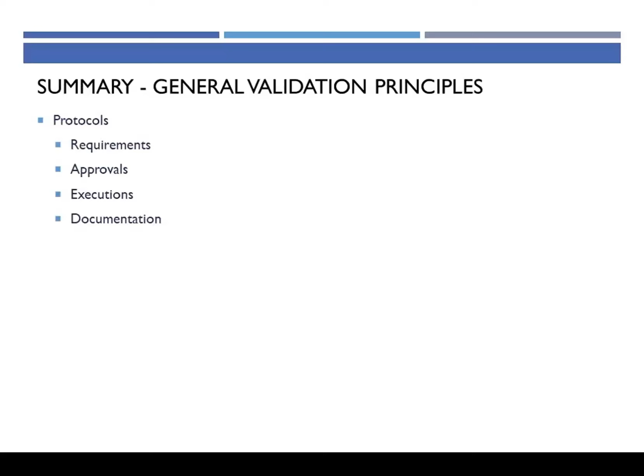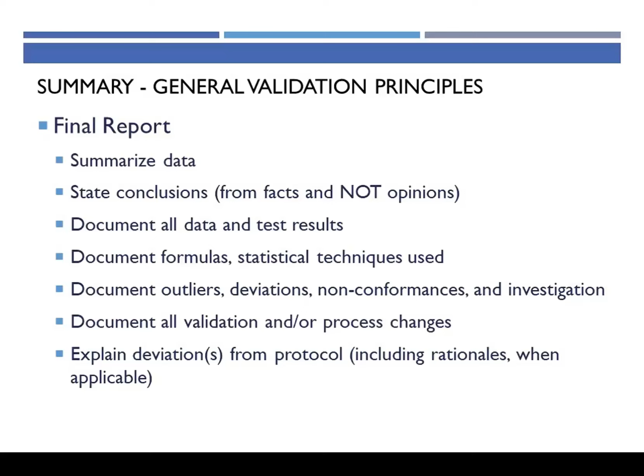You want to document all your test results. You want to document any formulas and statistical techniques that were used, like we calculated a CPK using this formula. You want to document anything that happened during your validation. Were there any deviations or nonconformances? How did you investigate them? Document all changes that were made and explain any deviations from the protocol. If the operator was supposed to pull 2 samples every hour and he forgot 1 hour, what does that mean? What are you going to do about it?